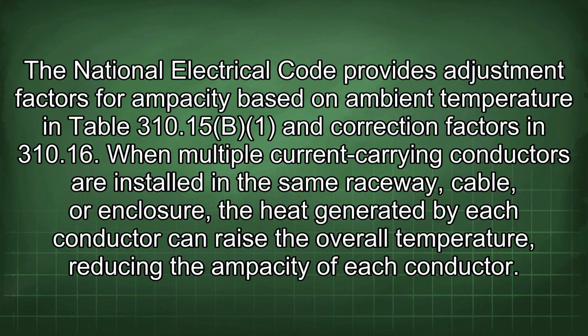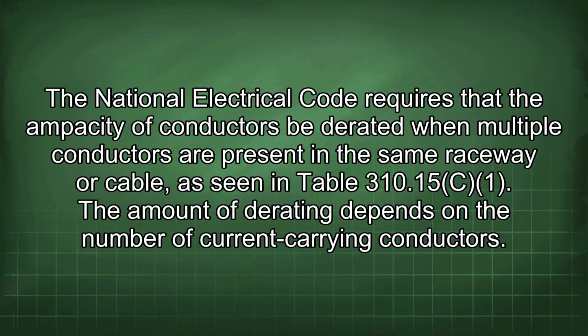When multiple current-carrying conductors are installed in the same raceway, cable, or enclosure, the heat generated by each conductor can raise the overall temperature, reducing the ampacity of each conductor. The National Electrical Code requires that the ampacity of conductors be derated when multiple conductors are present in the same raceway or cable, as seen in Table 310.15(C). The amount of derating depends on the number of current-carrying conductors.